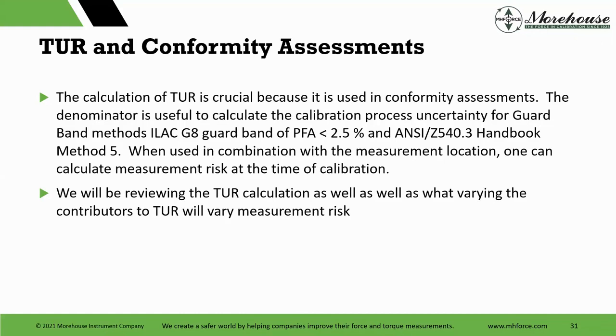In fact, the book Introduction to Statistics and Metrology, another great book, talks about that, and they put the blurb in. When they wrote this, they thought about it, and they make the statements of a 3-to-1 TUR, a 4-to-1 TUR, and they do not consider the measurement bias. So just remember that when you're looking at those other standards and someone says, hey, as long as it's 4-to-1, yeah, as long as it's 4-to-1 and the location is centered. They don't add the and.